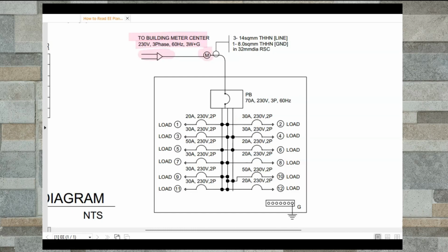Dito nakasulat, 3 na 14 square mm na THHN, that's for line side, tatlong linya, at isang 8.0 na THHN para sa ground, nakalagay sa conduit na 32 mm diameter na rigid steel conduit. Ibig sabihin yung ating piping ay naka-expose.